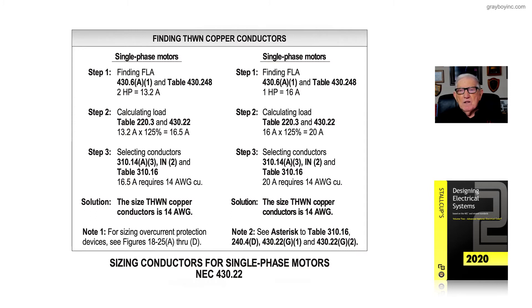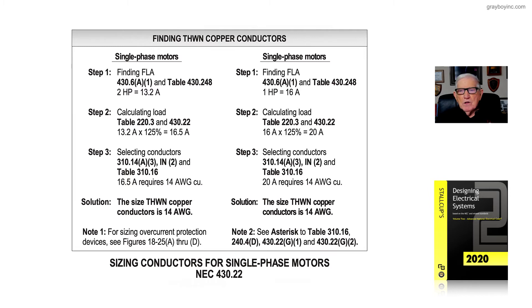Following the references of Table 220.3 over to 430.22 in Part 2, we apply the 125% rule times the Step 1 full-load current of 16 amps, and we come up with 20 amps.